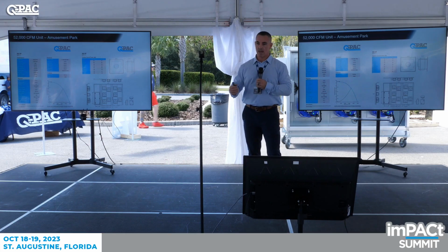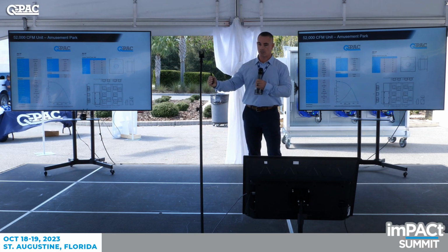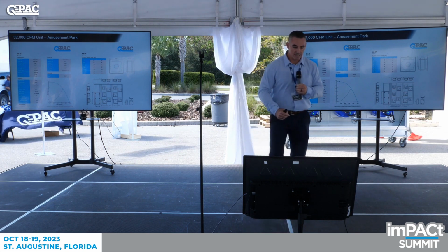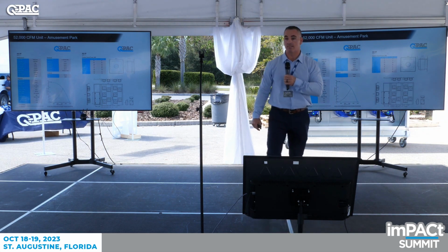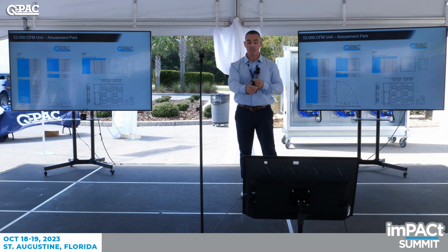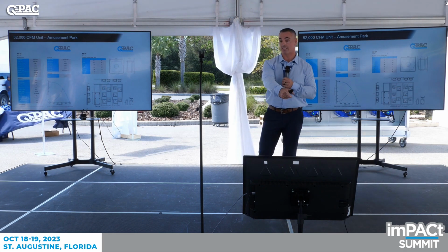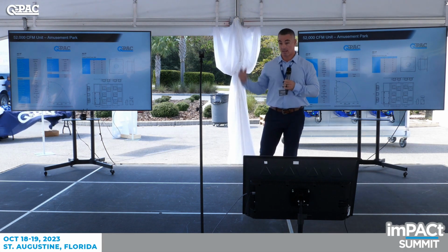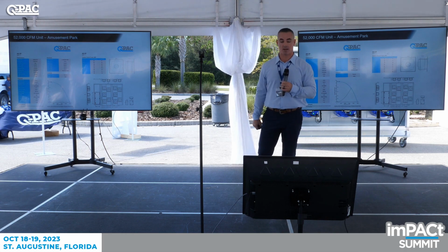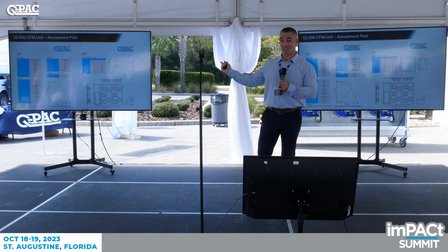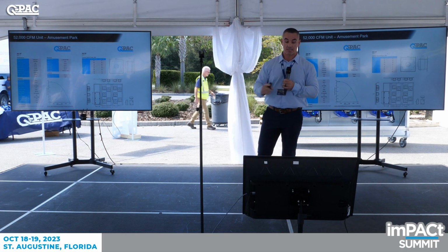So I always do that, and I'll run it up to see where we max out, and I still gave them 91% redundancy there. They're actually operating this system at 65% speed. Running full speed, running where they're at. So yeah, that's a good pickup because a lot of people wouldn't pick up on that, but it's intentional.